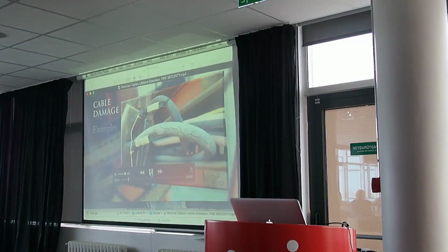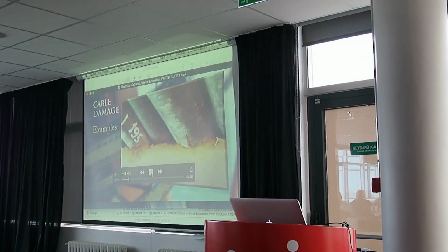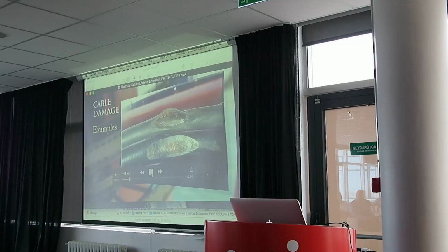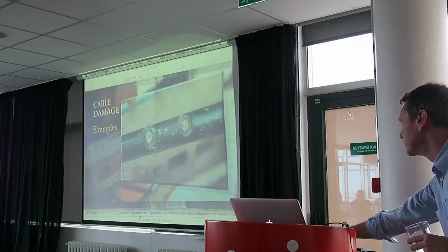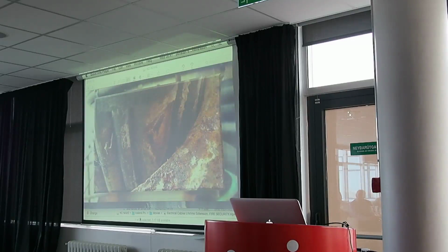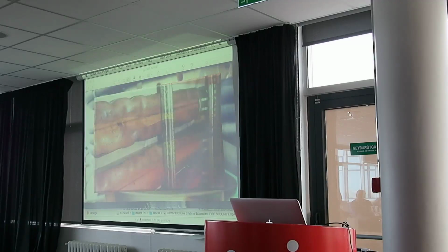Mechanical stress on cables and cable jackets is caused by vibration and vessel movement. These factors will reduce the lifetime of your cables. Damaged cables may be a serious safety issue once their integrity is lost. Tests have shown that damaged cables no longer meet their specification in terms of fire performance.